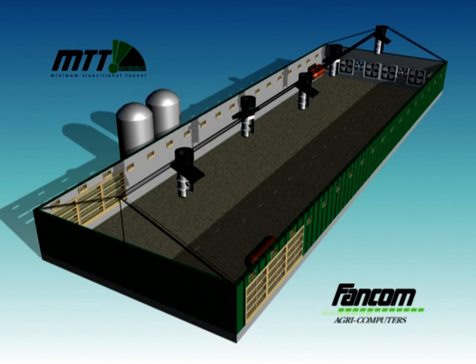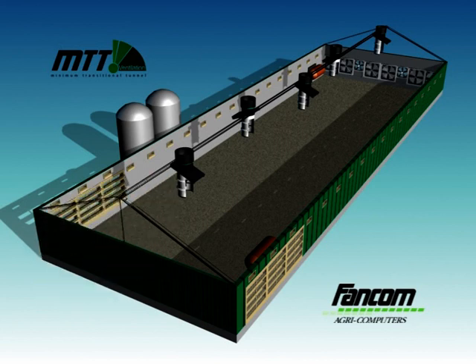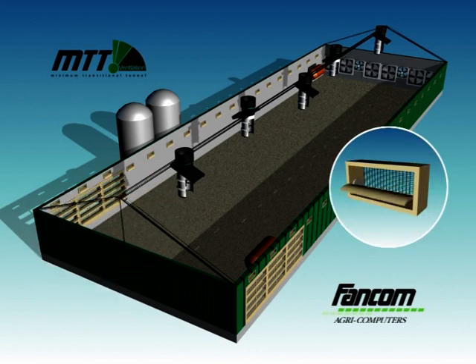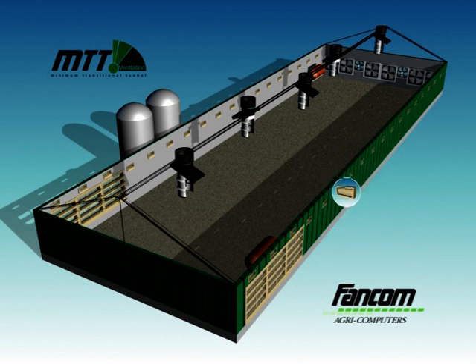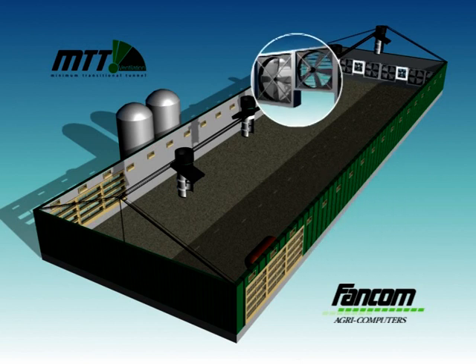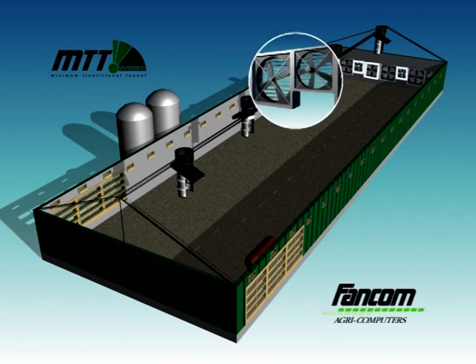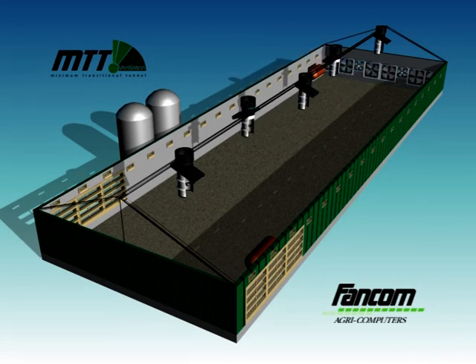The final phase of the MTT concept is tunnel ventilation that exhausts the heat produced by the birds. The air inlets are fully closed and the tunnel inlets are opened as required. The large fans in the rear wall are activated one by one, creating the so-called tunnel effect, where air flows over the animals at great speed.